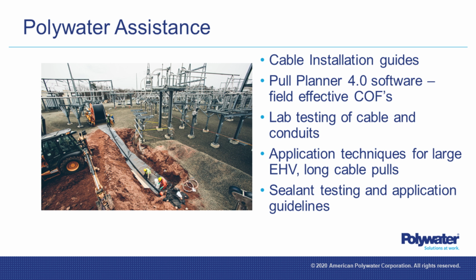So the industry tends to use a number that's out there, partly to be conservative when calculating cable pulls, but it's not necessarily real world. The pull planner has a vast database on these coefficients of friction for numerous types of cable jackets and conduit surfaces. By far, the coefficient of friction has the most influence, besides direction of pull, on the actual cable pull—the lower the coefficient of friction, the lower the ending tension and sidewall pressure.